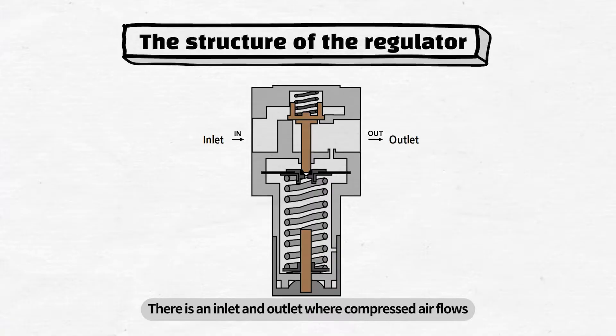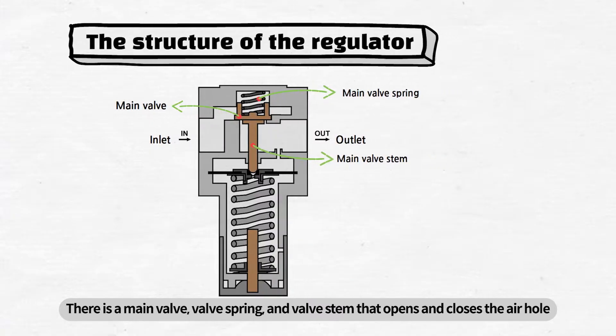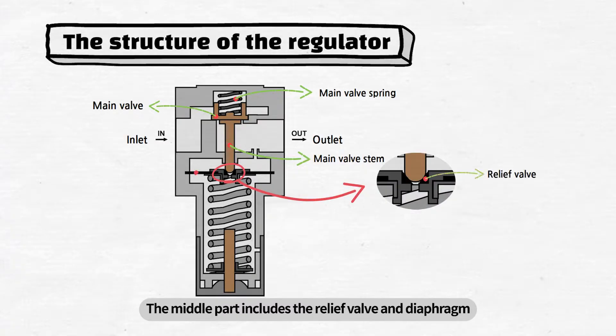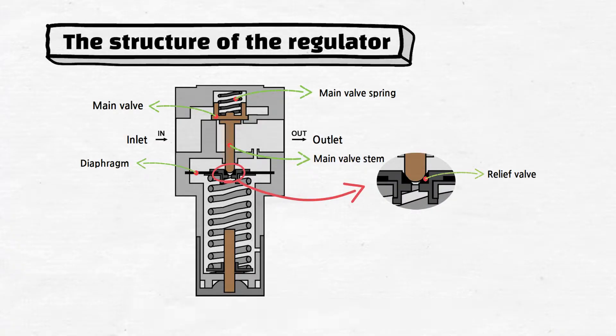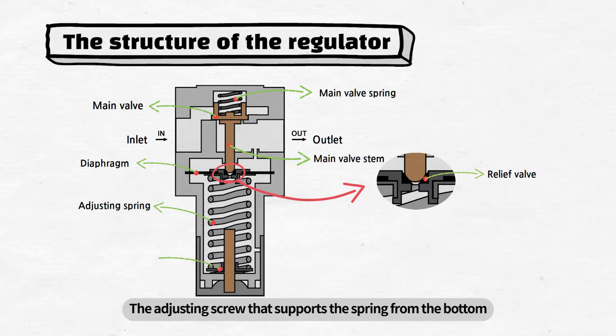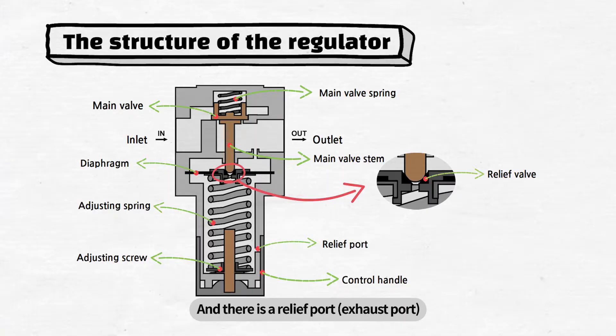There is an inlet and outlet where compressed air flows. There is a main valve, valve spring, and valve stem that opens and closes the air hole. The middle part includes the relief valve and diaphragm. Below, it is a pressure adjustment spring, which we will call the adjusting spring. The adjusting screw that supports the spring from the bottom, the control handle that adjusts the pressure settings, and there is a relief port.